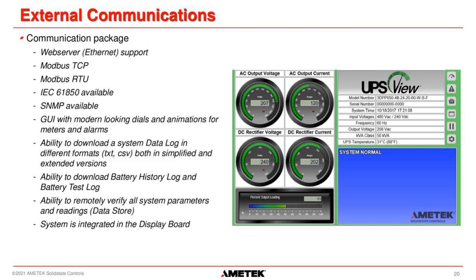The graphical user interface, or GUI, for the website has animated dials, so you can see voltages and currents, which show green or red if they go too low or too high, and you can also see the alarms. You can download data logs in additional formats compared to SCI Link. In SCI Link we just have text files, but here you can also download as a CSV. You can do simplified data logs that just show what alarm activated and at what time. Or you can use an extended version that shows what alarm activated at one time, and also all the voltages and currents of the system at that time.